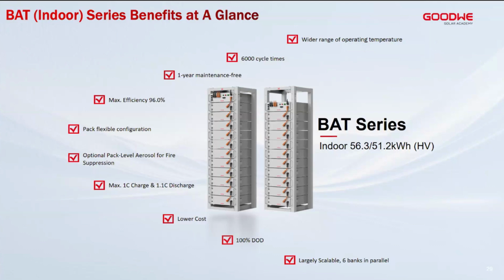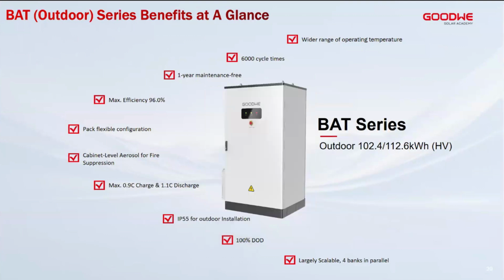The battery is of lower cost. Given that it's an indoor battery with advanced internal components, we've managed to reduce the cost of the product itself, but still ensure top quality because we are actually being audited by TÜV Rheinland. The product itself is very much meeting the standards for the African market. It's affordable for our C&I customers. Discharging this battery, you can reach up to 100% DOD. And scaling up the battery is very easy. You can do up to 6 banks onto one inverter. So either a 50 or a 40 kilowatt ET series can handle 6 banks of the BAT series. Now, comparing the first and this second BAT series, it's a matter of size, the rating, and basically the specs that will come in between.